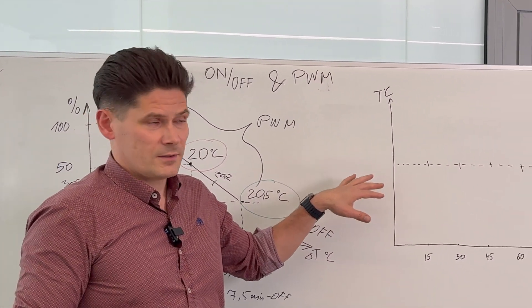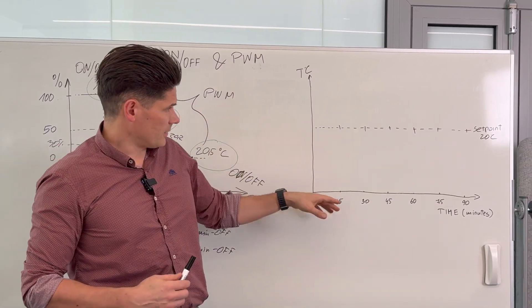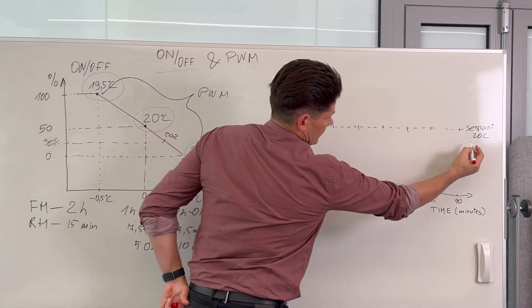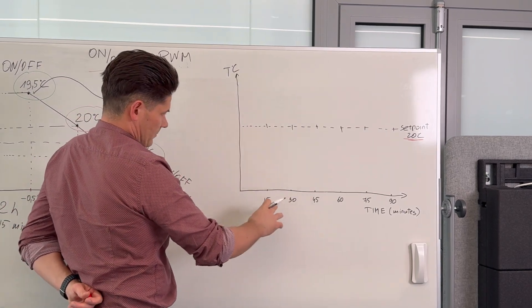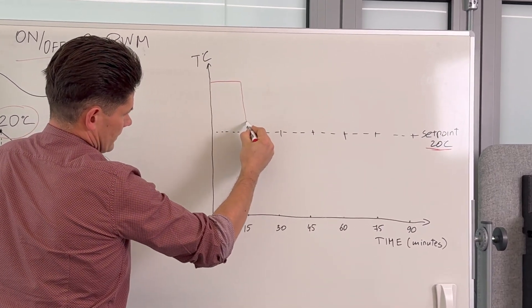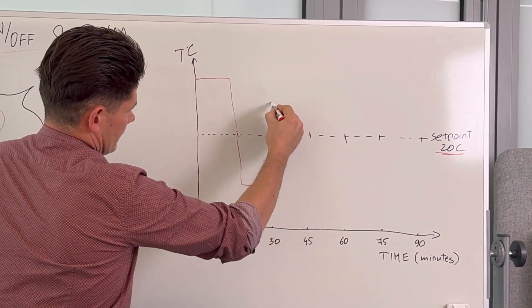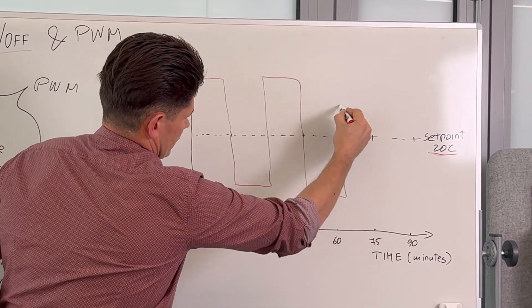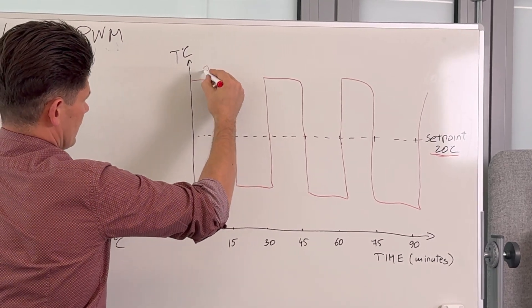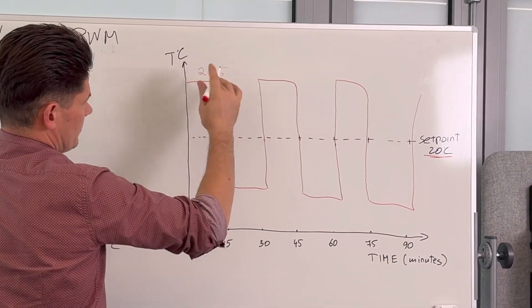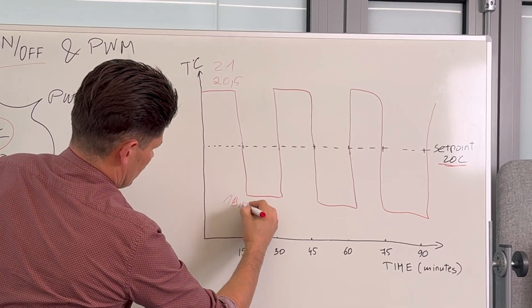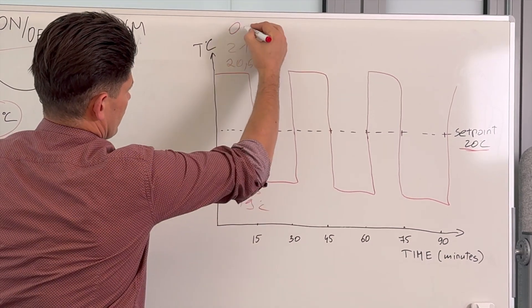I can show how temperature fluctuates in reality using on/off versus pulse width modulation control. With on/off control: the set point is 20 degrees. The actuator switches on and off repeatedly, and the temperature swings - it might reach 21 degrees or more on the high side, and maybe 19 or 19.5 degrees on the low side. This is how on/off regulation looks.